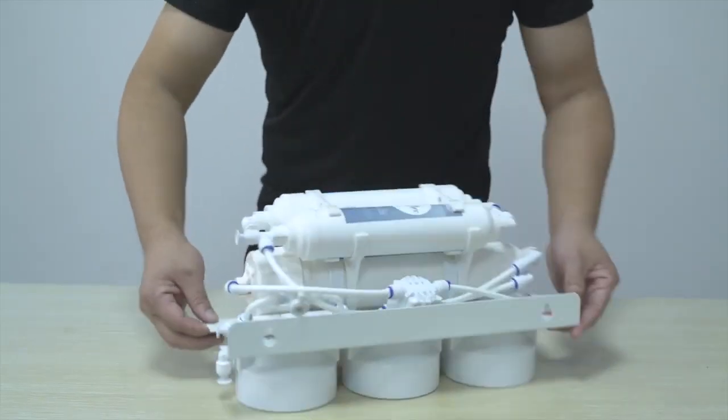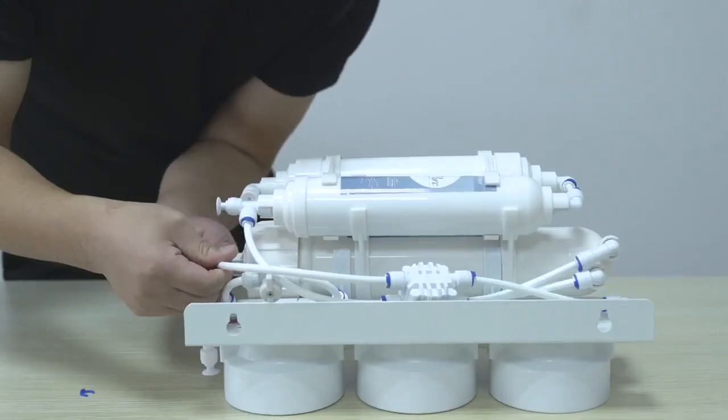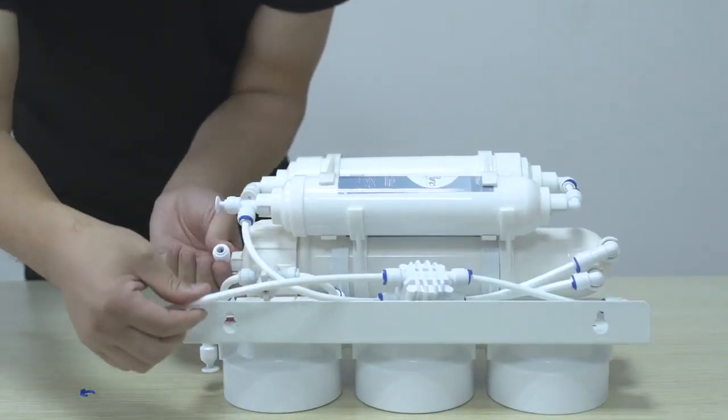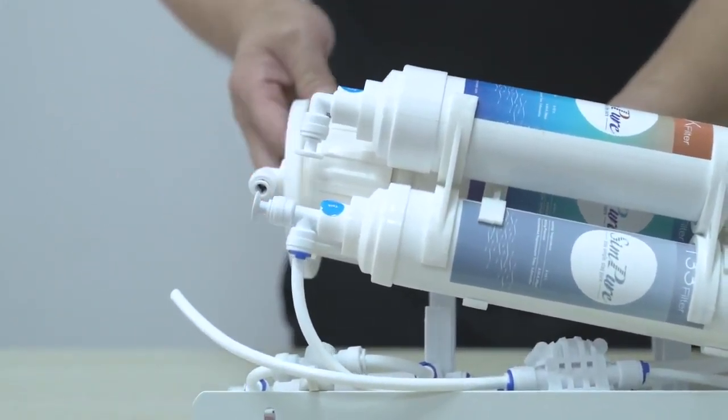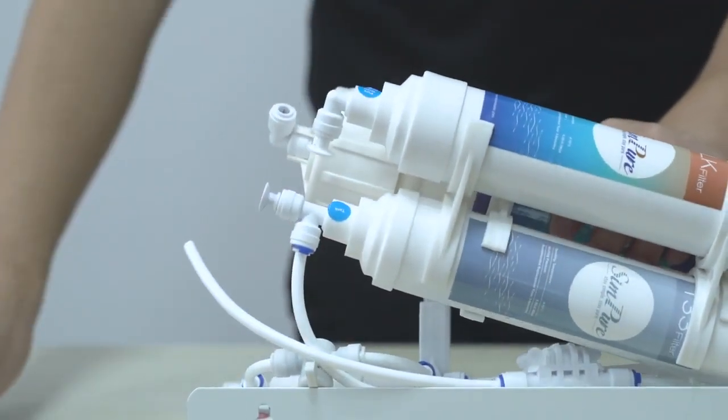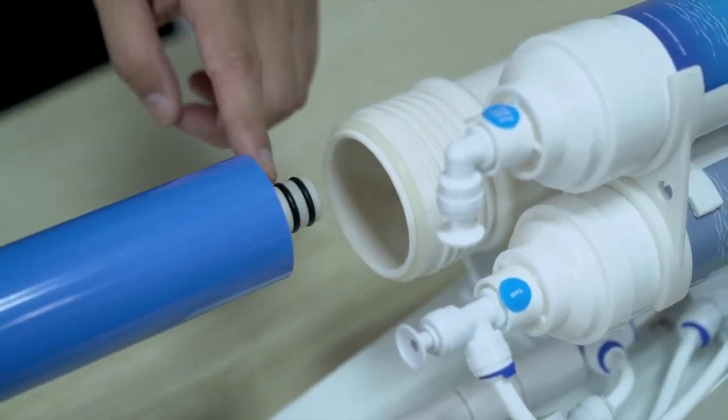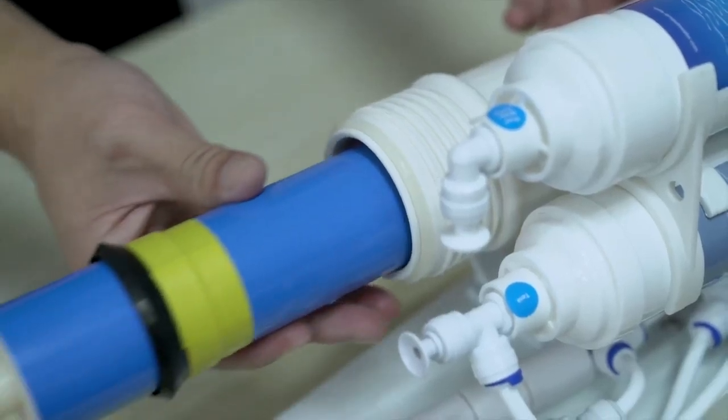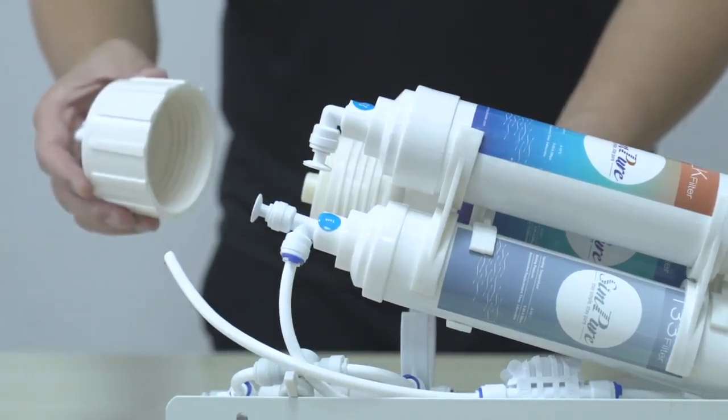RO Membrane: Remove the blue locking tube clip from the RO housing end cap and disconnect the PE tube. Unscrew the housing cap using the RO housing wrench. Reconnect the PE tube into the housing and check the O-ring inside the housing cap.